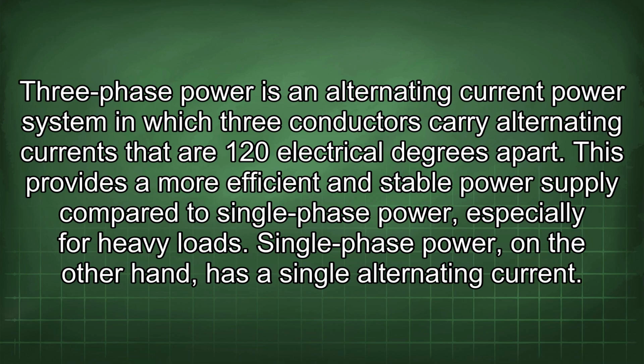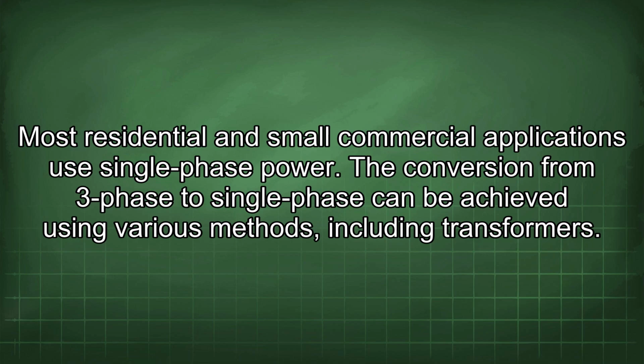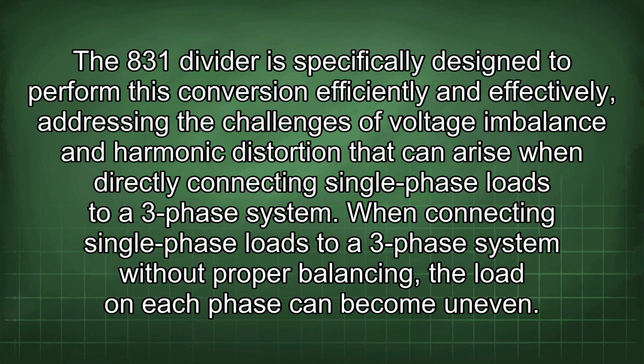Three-phase power is an alternating current power system in which three conductors carry alternating currents that are 120 electrical degrees apart. This provides a more efficient and stable power supply compared to single-phase power, especially for heavy loads. Single-phase power, on the other hand, has a single alternating current. Most residential and small commercial applications use single-phase power. The conversion from three-phase to single-phase can be achieved using various methods, including transformers. The 831 divider is specifically designed to perform this conversion efficiently and effectively, addressing the challenges of voltage imbalance and harmonic distortion that can arise when directly connecting single-phase loads to a three-phase system.